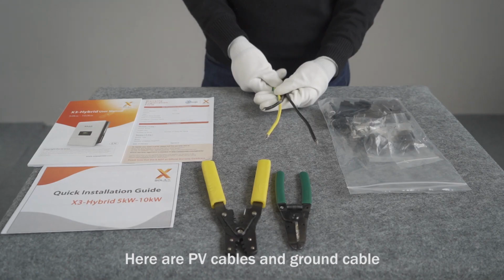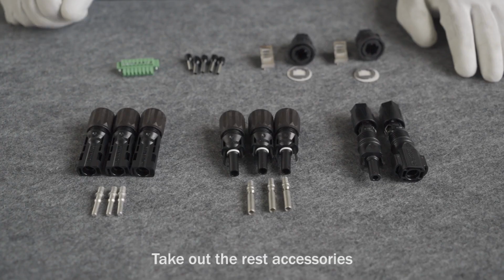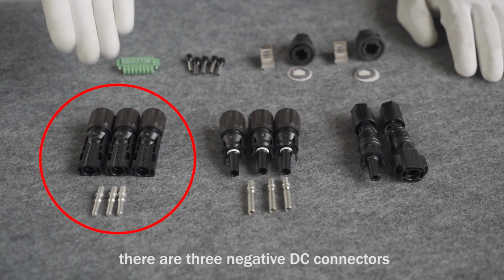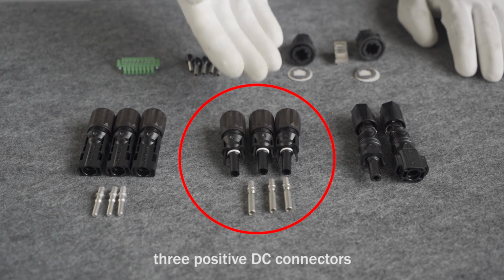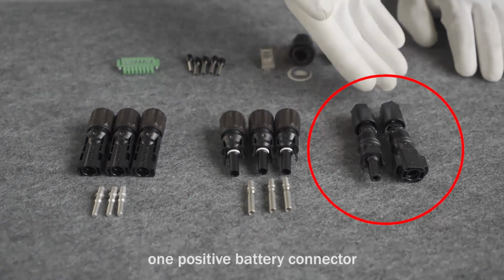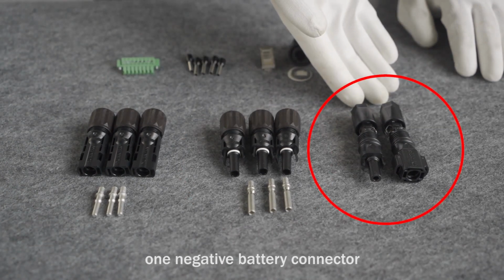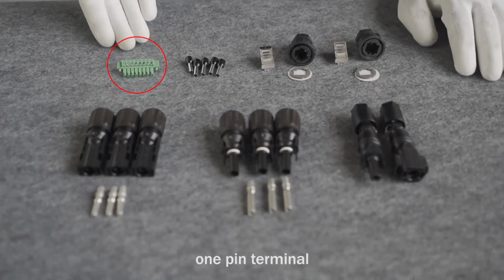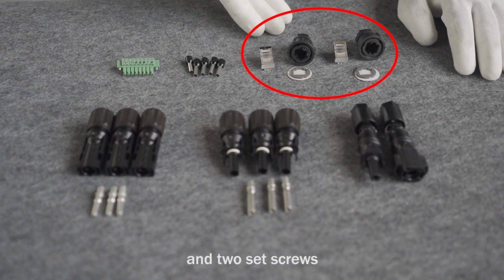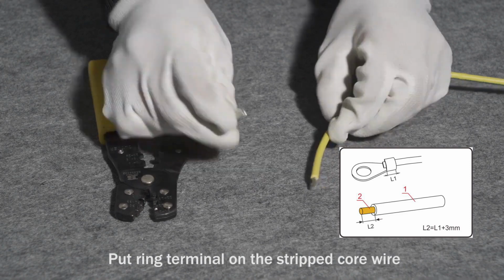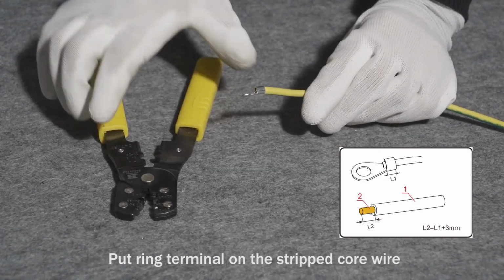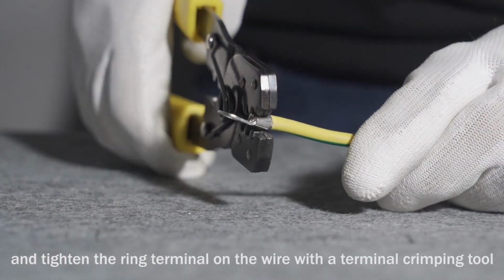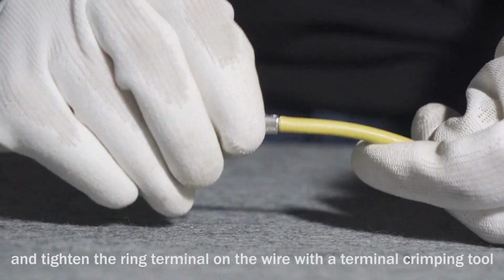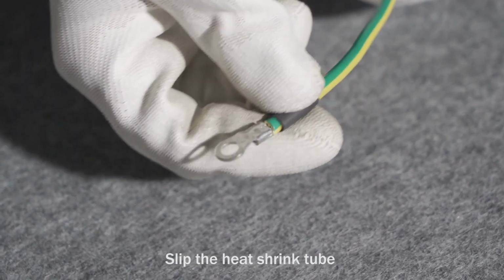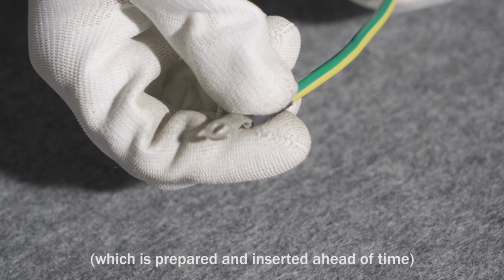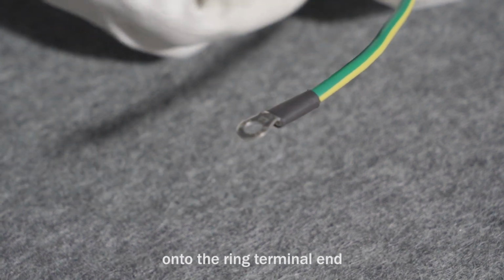Here are PV cables and a ground cable. Take out the rest of the accessories. There are 3 negative DC connectors, 3 positive DC connectors, 1 positive battery connector, 1 negative battery connector, 1 pin terminal, several AC terminals, and 2 set screws. Put the ring terminal on the stripped core wire and tighten the ring terminal on the wire with a terminal crimping tool. Slip the heat shrink tube, which is prepared and inserted ahead of time, onto the ring terminal end.